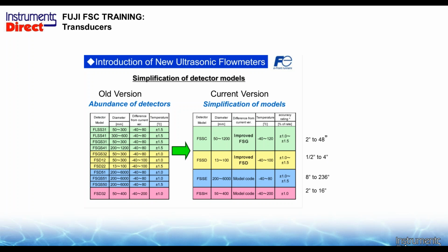The different flavors of transducers for the Portaflow-C. They do change the transducers every couple of years for whatever reason. They're getting better and better all the time, but you can still use a lot of the legacy transducers, which are pictured here on the left-hand side there. So they do have, there are on the drop-down menu, the different transducers here. Here's the most current transducers in the last year or two. Again, they just have less transducers that cover a larger field there.